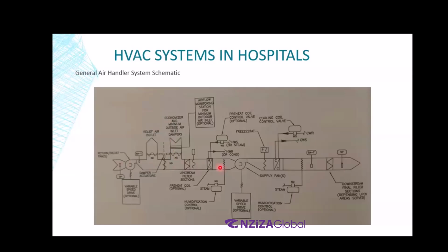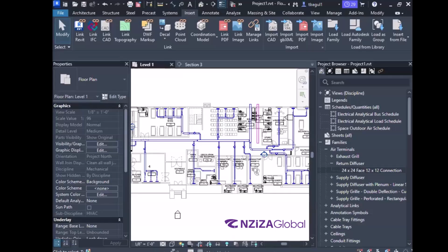Alright? That is one reason. Second reason is your coils, your fans are sized for a maximum possible capacity. If we don't have a relief and we keep on adding to this, the air CFM will just keep on increasing. Does that make sense? Does that answer your question? Any questions online? If any questions, please drop it in the text. We will take it. Okay, by the way, are the dots connecting now? What we are trying to do from day 1 over here?